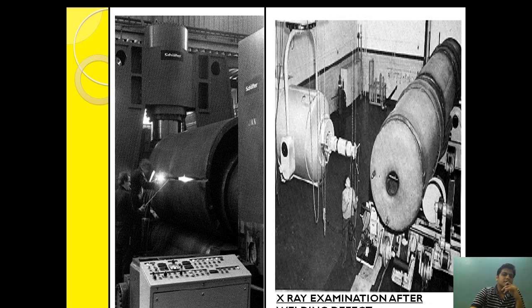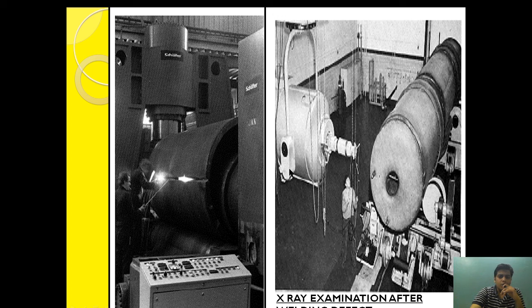Now we will see how the hemispherical end is made in a boiler. The hemispherical body is molded, rolled out, and then the two parts are joined by precision welding. After welding, the welding seams are monitored using X-ray inspection to ensure there are no welding defects. If a defect is found, that part is scrapped, welding is redone, and X-ray inspection is carried out again to ensure the pressurized cylindrical vessel is welded properly.